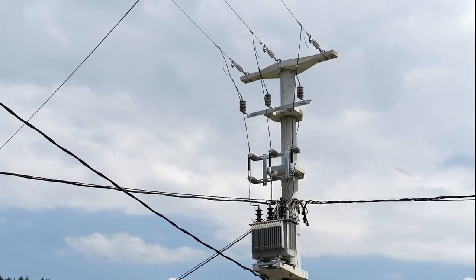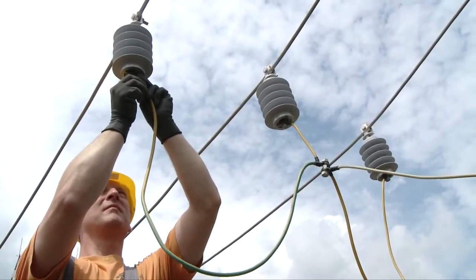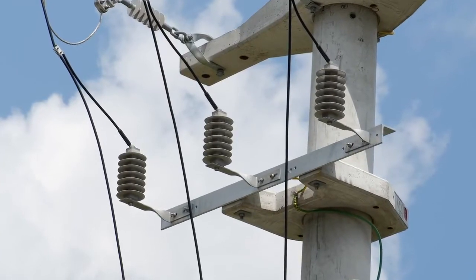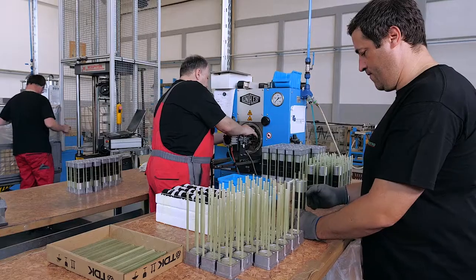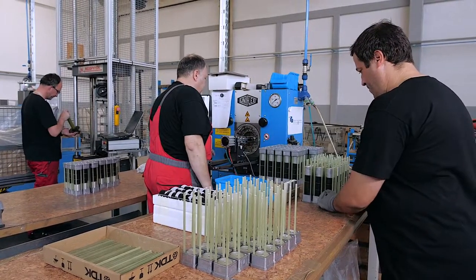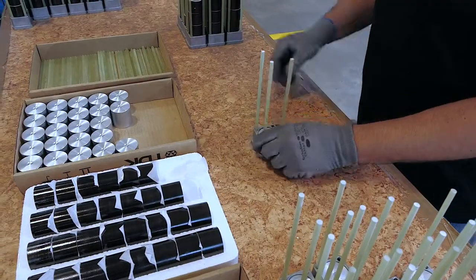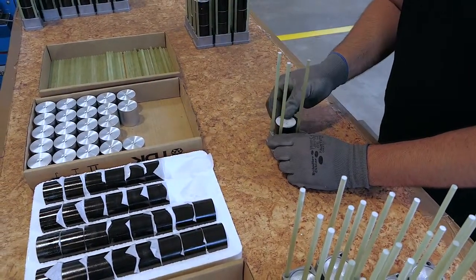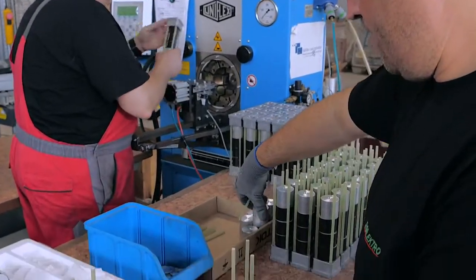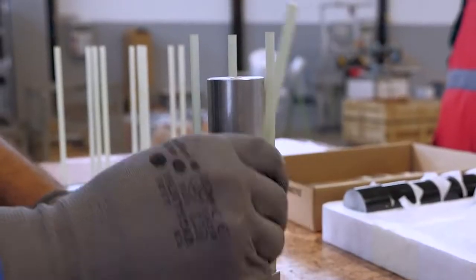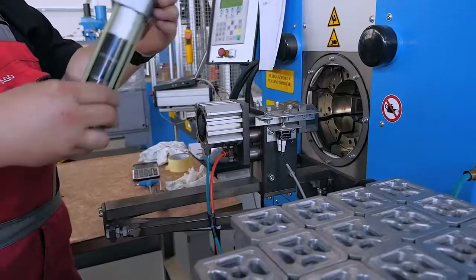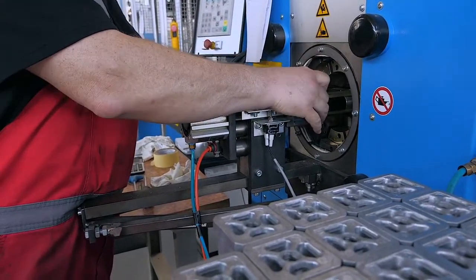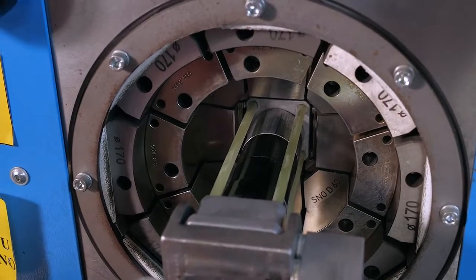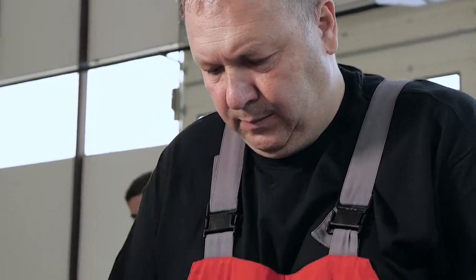We also produce Class 1 and Class DH medium voltage metal oxide surge arresters of up to 44 kilovolts. These surge arresters have been tested in the accredited Italian laboratory CESI. Their quality is ensured by a low leakage current and a robust construction, with varistors directly enclosed in silicone. The varistor block is assembled based on the measured voltage of the varistor using a unique control device. The rigid construction with epoxy rods allows high bending and torsion moments.